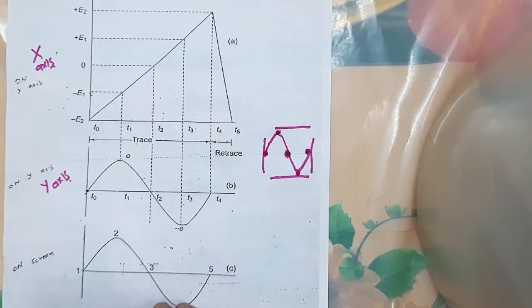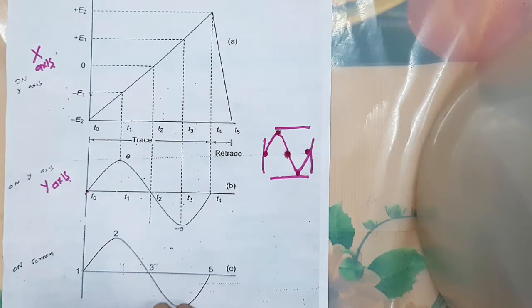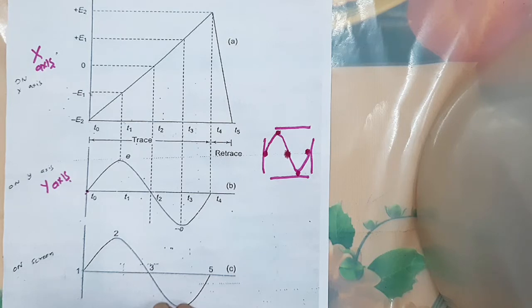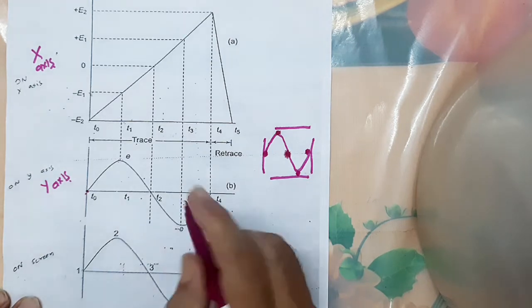So we are completely understanding this step by step. At time T0, the sweep voltage or sawtooth voltage is minus E2, and the negative horizontal voltage moves the spot to point 1 on the screen. At this instant, the signal voltage is zero, so the spot rests at the left end of the zero line. At T1, the sawtooth reaches minus E1 — more positive than minus E2 — moving the spot to point 2 on screen. At this instant, the signal voltage is at its positive peak value E, so the point represents maximum upward direction of the spot.